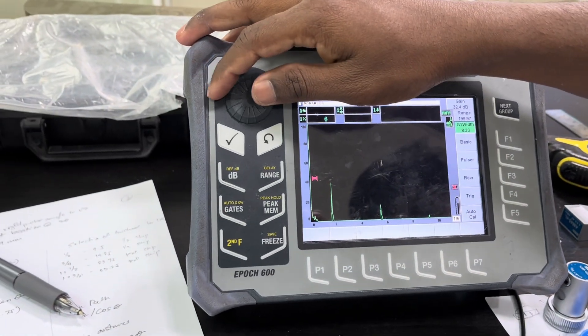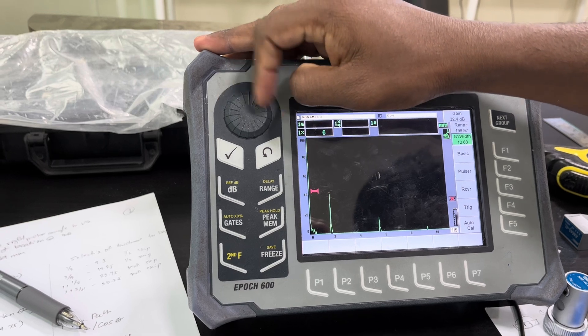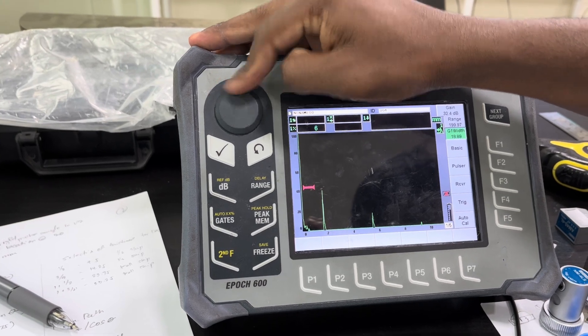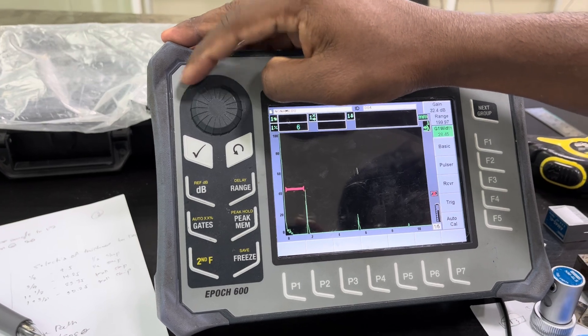When I place the probe towards the 25 radius, the first back wall echo is at 25, the second back wall echo is at 50, and the third back wall echo is at 75.